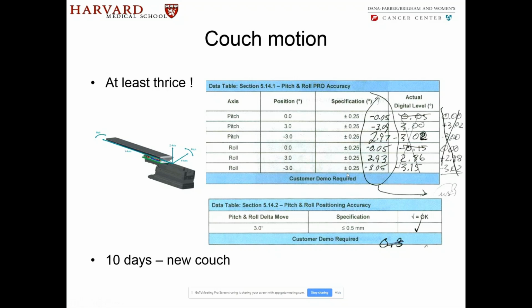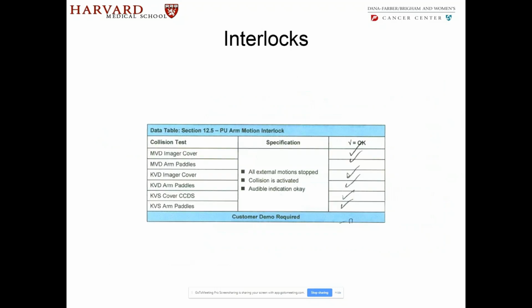So the process of acceptance can get quite tricky if things are not working as they are expected to be working. It's stressful for the engineers, it's stressful for us, but most importantly, do not give in when they say, yeah, well, you know, it's 0.5 mm or plus or minus 0.25, it's just a little beyond that. Do you actually even use the couch for that purpose? That's one of the arguments that they will try to make with couch or something else. Just say, nope, this is your spec. It has to be met. Otherwise, we don't accept your machine. It may delay the process, but at least you know that you will get a system which is in proper condition to begin with. Then you go out, you check the interlocks, everything else, and you're done. So now we have accepted the machine.